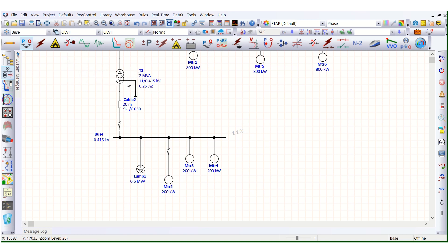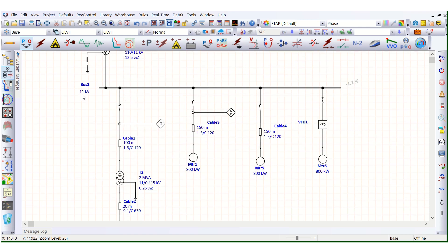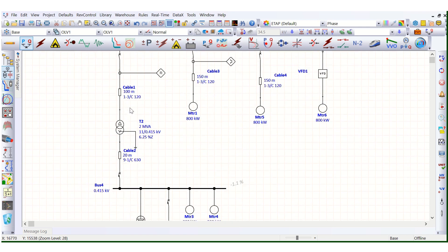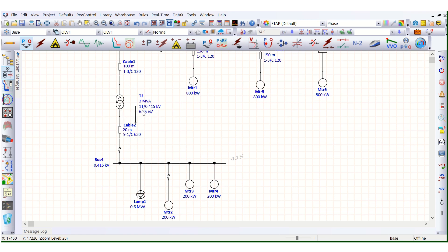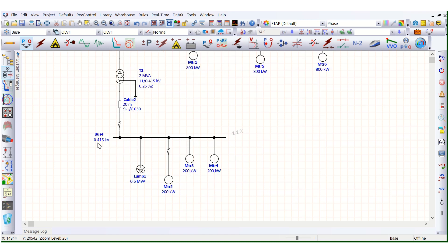Here you can see the transformer rating in this network — this is an 11 kV by 415 V, 2 MVA distribution transformer, with a percentage impedance of 6.25%. Connected to this 415 V switchgear bus, a lump load of 0.6 MVA is connected.